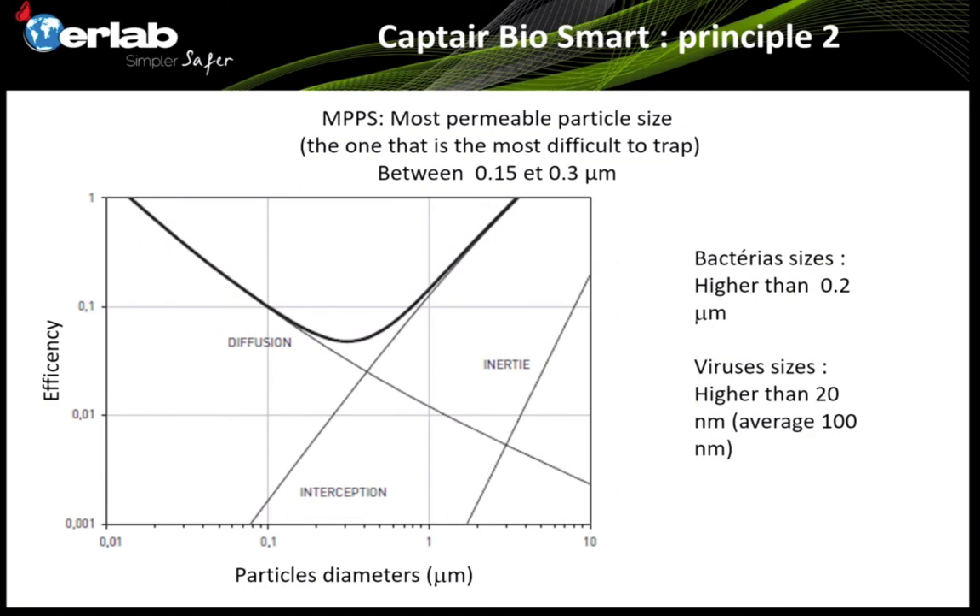As an example, we can see that the smallest bacteria have a diameter around 0.2 micrometers, and there is no problem trapping them. For virus sizes, most have dimensions higher than 20 nanometers and according to the MPPS test, they are trapped with no problem. It is also good to know that most of the time bacteria or viruses are not carried alone — they are carried by little drops of water or dust, so we are typically trapping a mix of virus plus dust or water droplets.